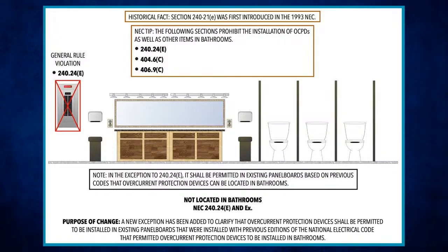If you had an old commercial building and happened to have that in the bathroom, here's what would happen: if you look at March 15th, 1972 - and this is one you have to be very aware of as a journeyman, contractor, master, anybody out on the job - anything installed before then is grandfathered in. Then from March 15th, 1972 to April 16th, 1981, everything was up to whatever the code was at that time. But if you made any changes, a major portion thereof, 50% or more, you had to bring it up to whatever the current code was at that time.